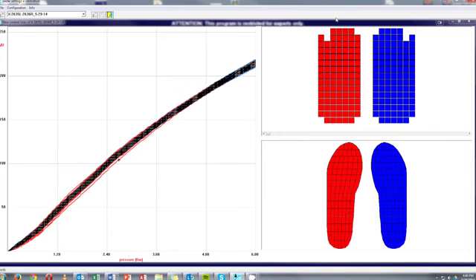The combined calibration lines are each individual sensor's calibration curve combined in a single picture. As we can see, the y-axis contains the A to D values, and the x-axis contains the pressure values. Notice if I click on an individual curve, you can see which sensor that corresponds to. Similarly, if I click on a sensor, I can then see its curve in the calibration curve.